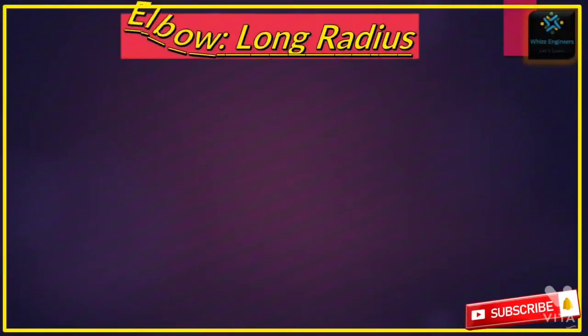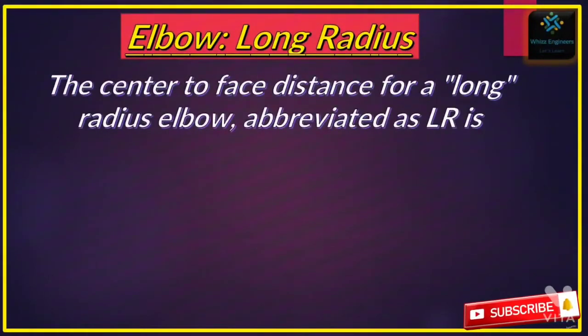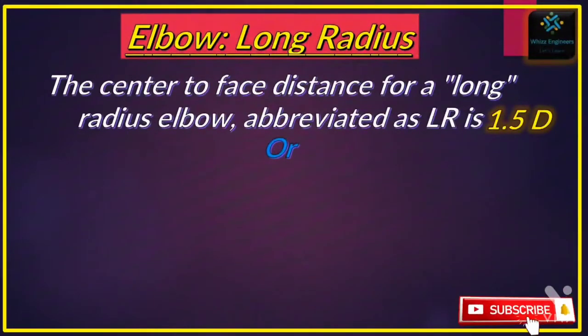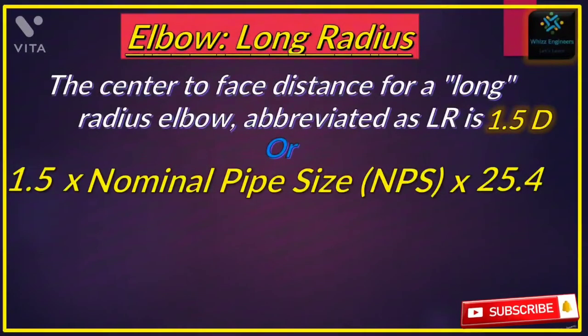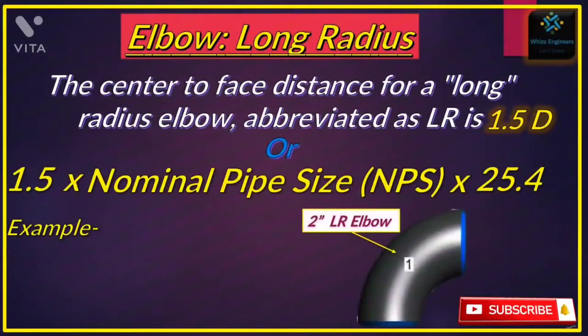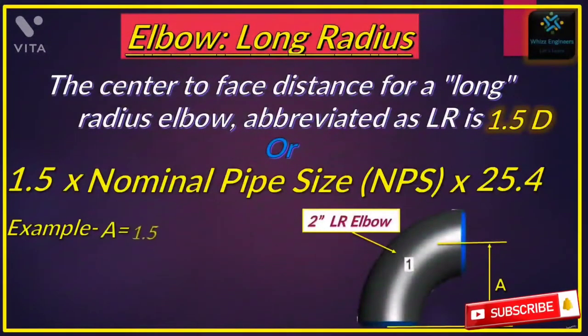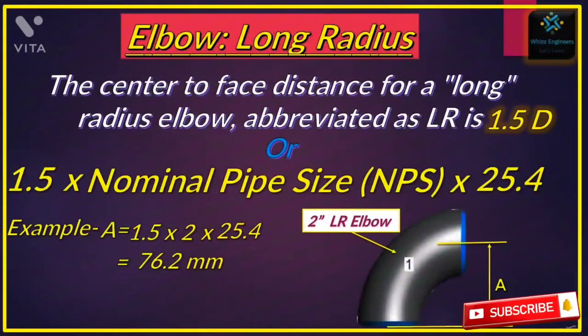First we will see the long radius elbow. The center-to-face distance for a long radius elbow, abbreviated as LR, is 1.5D. If you calculate it in mm, it will be 1.5 multiplied by the nominal pipe size multiplied by 25.4, because 25.4 mm is equal to 1 inch. For example, if we have a 2-inch LR elbow, the center-to-face distance A is equal to 1.5 × 2 × 25.4, so A equals 76.2 mm.